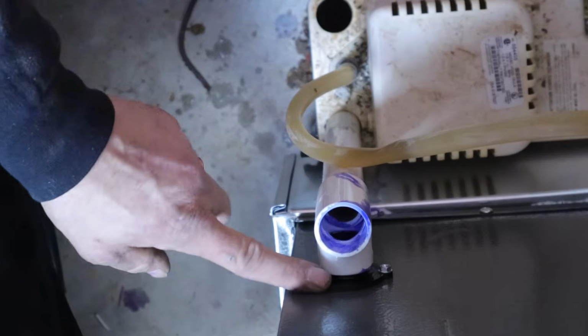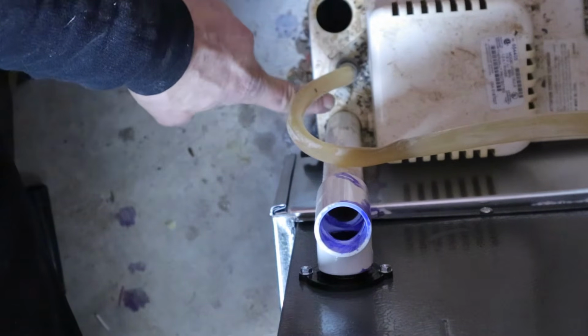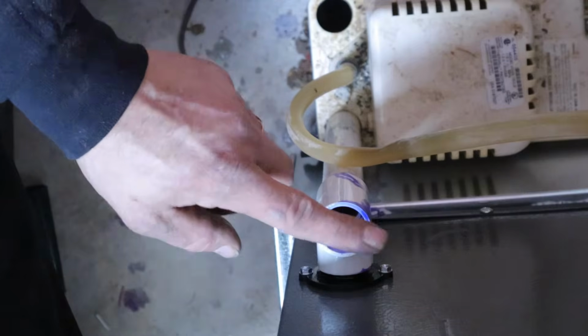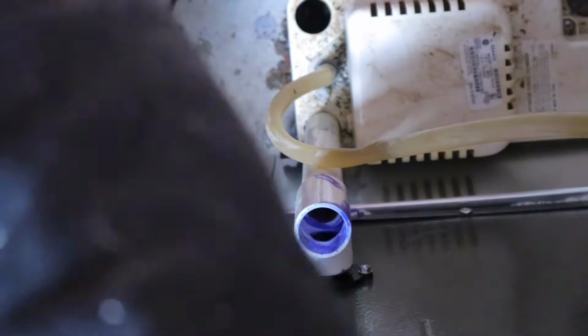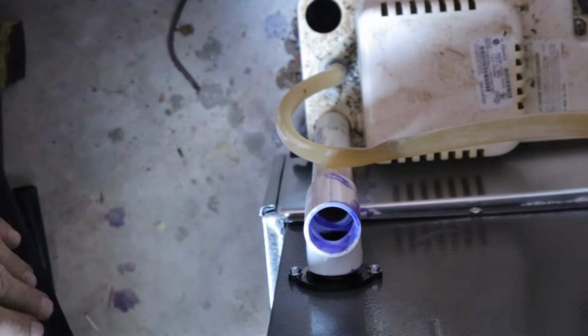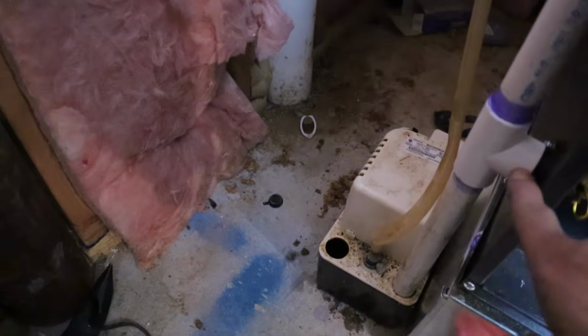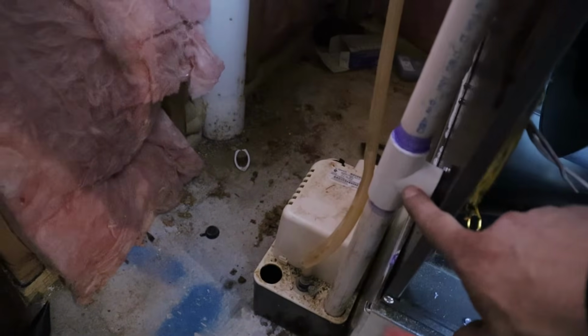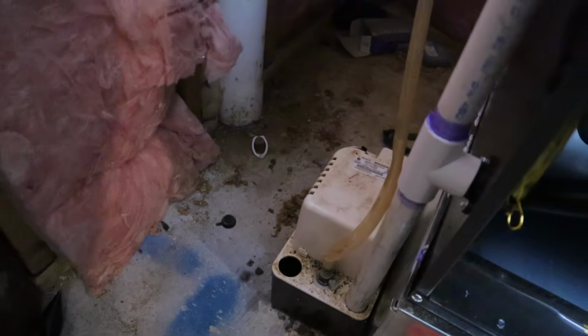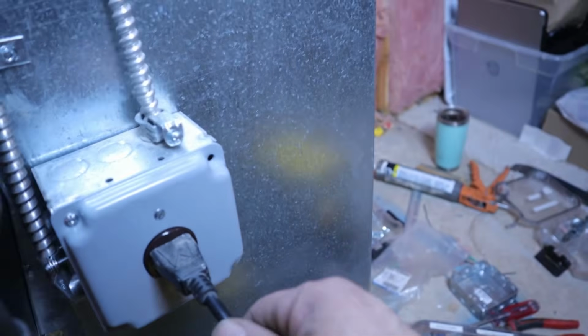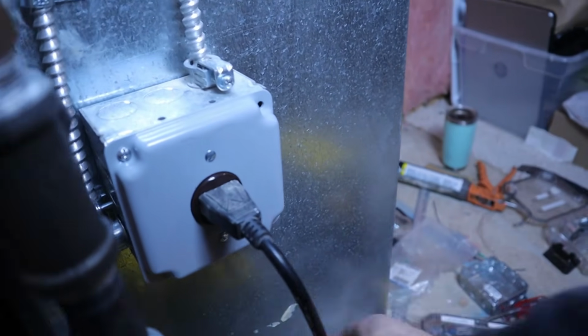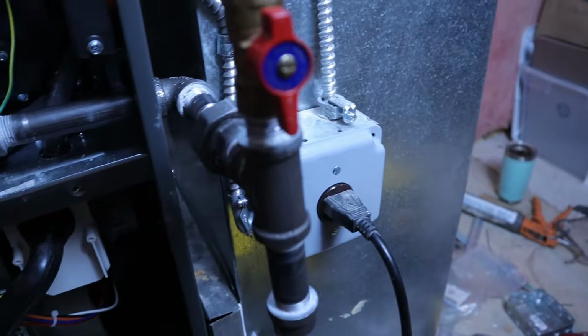Alright, so now we got our drain coming out for the furnace, going straight down into the condensate pump. Now I'm just going to run up and into the drain line for the A coil. So now we got our drain line from our coil going down. It's teeing off into the condensate that's going to be coming out for the furnace, and everything goes right down into the pump. And our pump, the cord, we got it plugged in here to the outlet that we put in. We're going to strap this down so it's not hanging out there, and then we're going to start connecting the flue pipes.